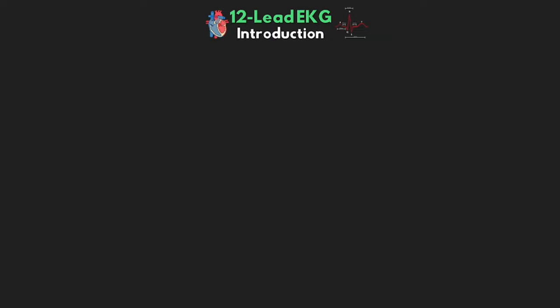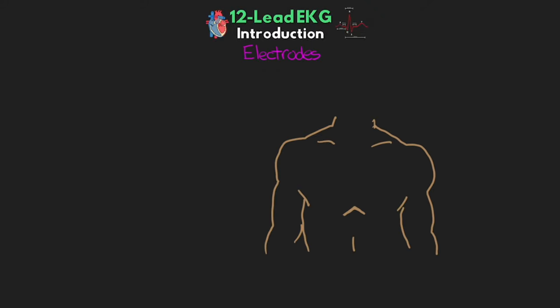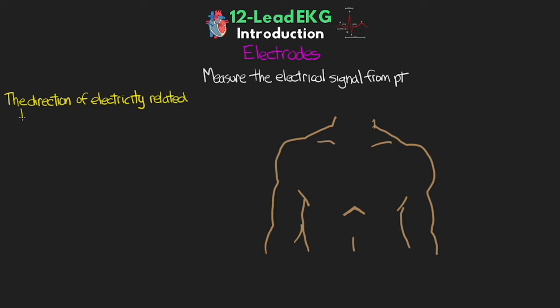Let's move on and talk about the EKG system and the different parts of how it all works. First, we have our electrodes — these measure the electrical signals and are the little stickies that we put on the patient. From there, we hook up the wires or leads to those electrodes. We have positive and negative leads — something we call bipolar, which can be both positive or negative depending on how we're using them — as well as a series of positive leads.